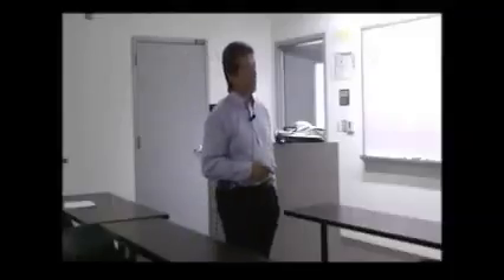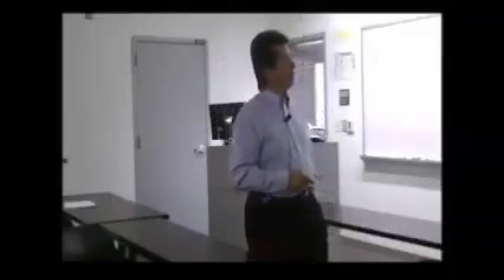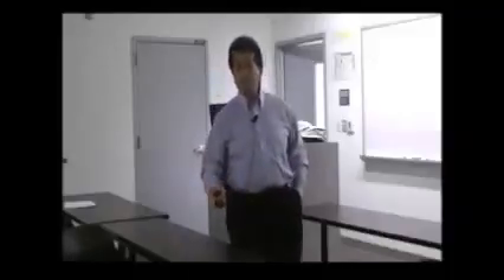Okay? When you pop your head above a ceiling tile and it's cooler up there than it is down in the room, you probably have some leakage, right? Okay. Exhaust inspected and cleaned on a regular basis. Filters cleaned. Okay. Areas subject to leaks inspected regularly. So if I have water leaks, drywall especially, okay. You know, sometimes it's not a big deal. It gets wet once, maybe twice. But if it gets saturated on a regular basis, you can tell that it starts to degrade.